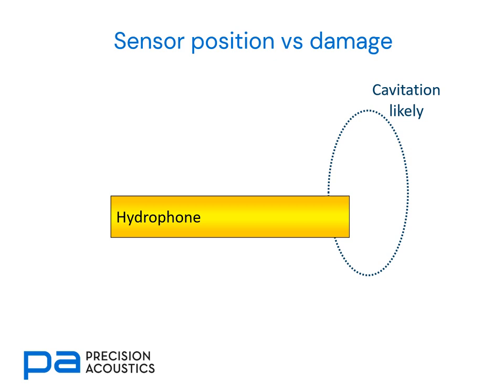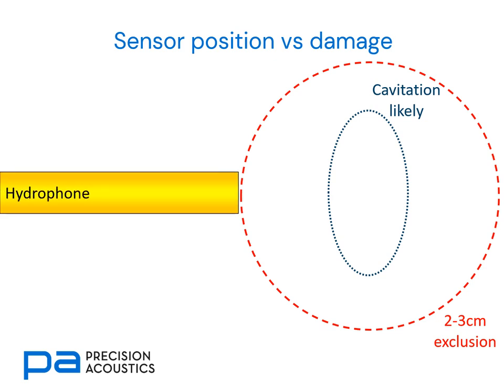So what can we do to try and help? If we can identify a region of interest where cavitation is most likely, placing a hydrophone within that region of interest is unlikely to be a wise course of action — should we get an inertial cavitation event, damage to that hydrophone is highly likely. A far better strategy is to identify an exclusion region around the region of interest. By placing the hydrophone or passive cavitation detector outside of that region, whenever we have cavitating bubbles, even if there are inertial events occurring within the region of interest, the hydrophone is safe from damage.